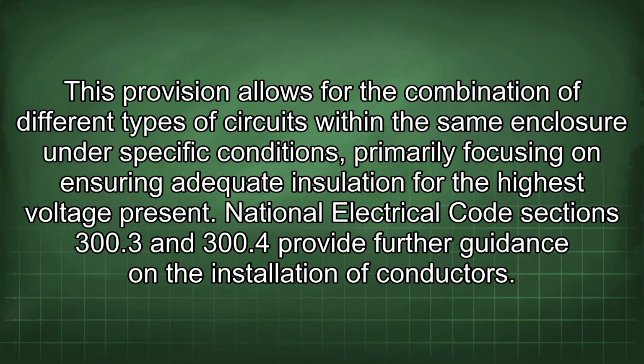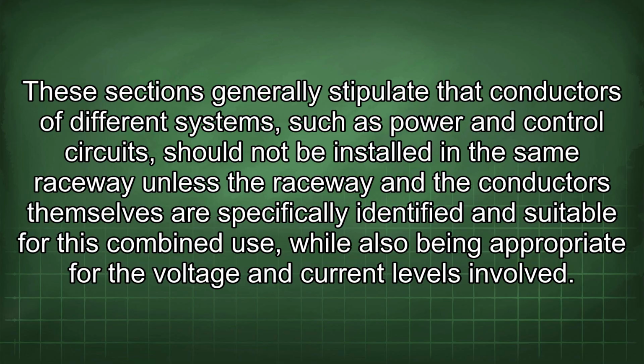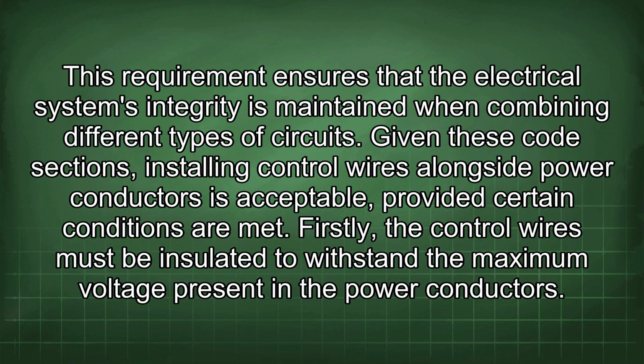National Electrical Code Sections 300.3 and 300.4 provide further guidance on the installation of conductors. These sections generally stipulate that conductors of different systems, such as power and control circuits, should not be installed in the same raceway unless the raceway and the conductors themselves are specifically identified and suitable for this combined use, while also being appropriate for the voltage and current levels involved. This requirement ensures that the electrical system's integrity is maintained when combining different types of circuits.